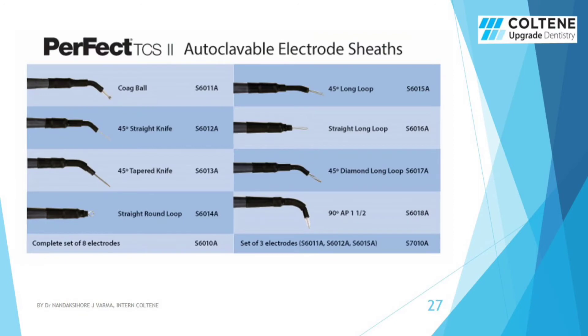Here I have shown images of autoclavable electrode sheaths available with Perfect TCS2, which includes a set of 8 electrodes: coag ball, 45-degree straight knife, 45-degree tapered knife, round straight round loop, 45-degree long loop, straight long loop, 45-degree diamond long loop, and 90-degree AP 1½.